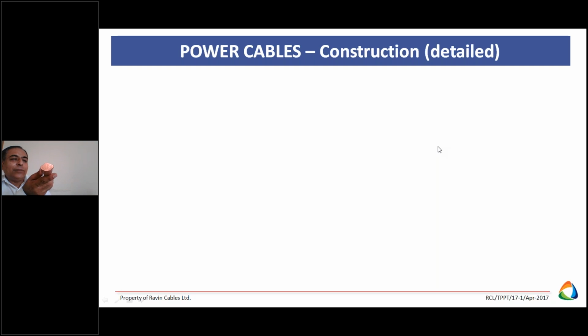But in LT cables, voltage is very less, so we make shape conductors, which gives a lesser overall diameter of the cable. This requires less material, insulation, and energy - less material means cost optimization and proper utilization of materials. That's why we use shape conductors.